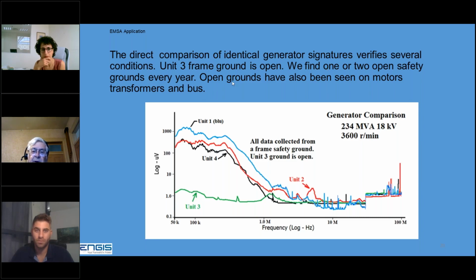We've seen it on motors, generators, transformers, and isolated phase bus. Particularly in very old plants, that safety ground can open up from corrosion. Also in some brand new plants, and in fact that was the case here, these generators are only about 5 years old, and this 4-aught cable went into the ground, but it didn't connect to anything. So that was bad construction.